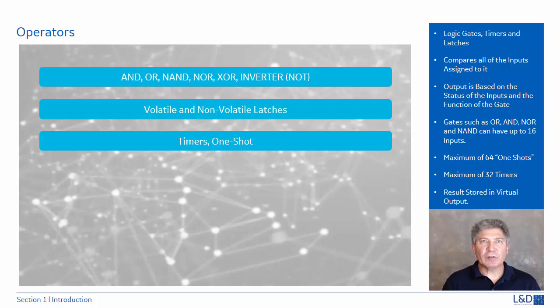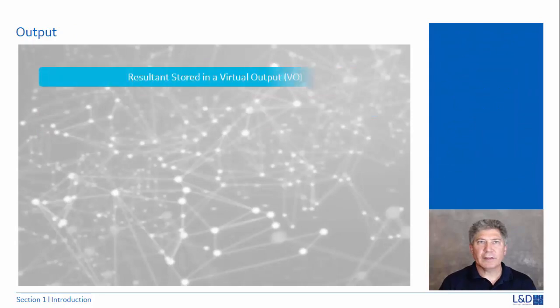The output or the resultant of the operator is stored in a virtual output. In FlexLogic, the results of the operator are stored in an output. That output is known as a virtual output. There are 96 virtual outputs in the UR.